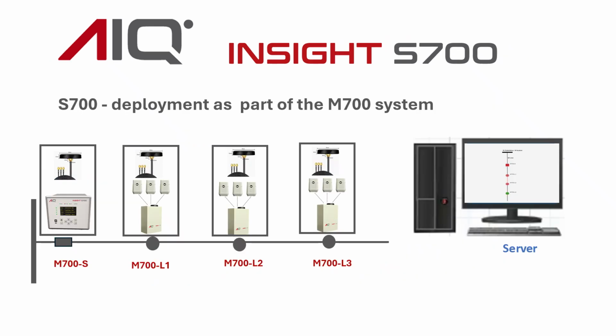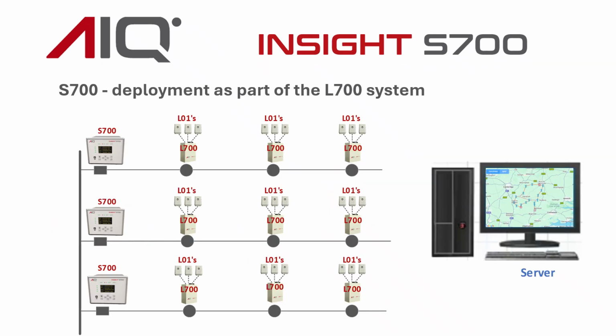Instead of standalone operation, S700 is also deployed as part of the Insight M700 transient fault localization system as a station node. This is covered in a separate video on the M700. Similarly, S700 is deployed as part of the Insight L700 fault localization system. This system will be deployed at each outgoing feeder and form a substation node of each feeder. This is covered under a separate video on the L700 system.